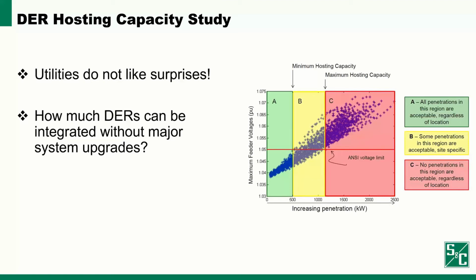The study applies either a probabilistic or deterministic approach, meaning that if there is some unknown in the system as far as the size of the DERs or the location in the system, then we can run some sort of stochastic scenario, which means that it's scenario-based, a Monte Carlo-based approach. There are different approaches for such analysis, or it could be deterministic in the sense that the utility knows exactly where those DERs are going to be placed based on the request that they received. The example shown here is from a study we performed for a utility in the US.